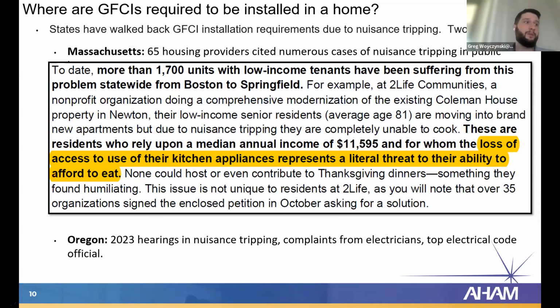Oregon has done something similar. They've done something a little bit more proactive, where they've also seen cases of nuisance tripping. And they've said for your major appliances that aren't going to be moved, you're probably not going to have water splashing on the receptacle behind them, for example. You don't need a GFCI. You don't even need to install one in the first place. So there are some states that are taking action on this issue.